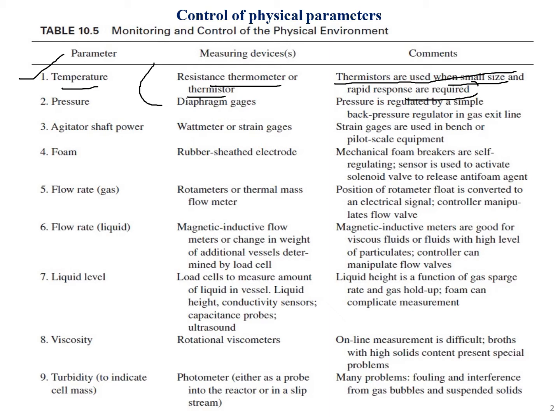The fourth point is foam. Foam is measured with the help of a rubber-sheathed electrode. Mechanical foam breakers are self-regulating, and a sensor is used to activate a solenoid valve to release an anti-foam agent. Foam is not a good sign whenever it is produced, and leads to a lot of consequences.